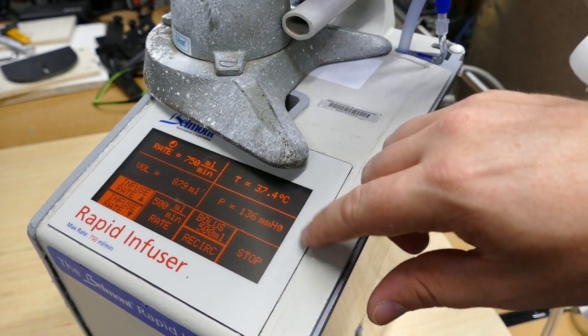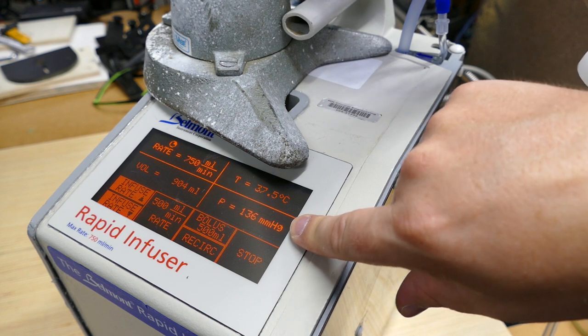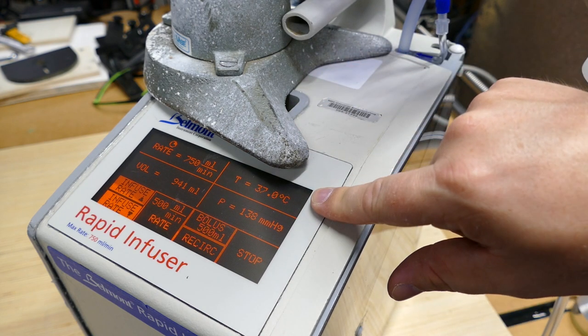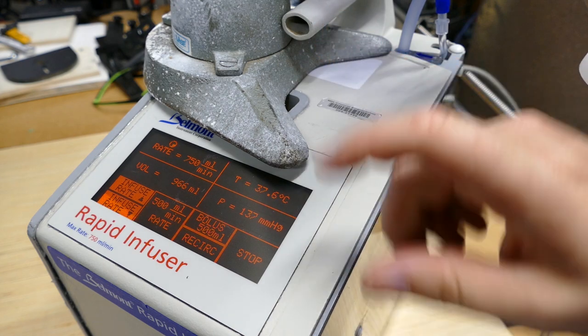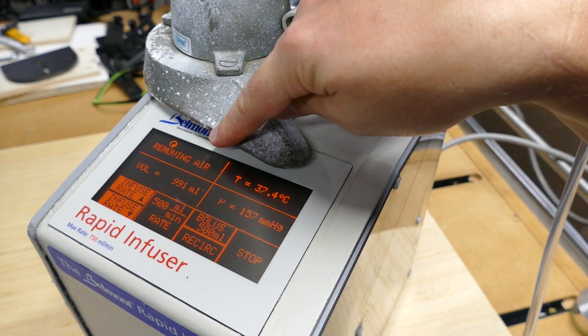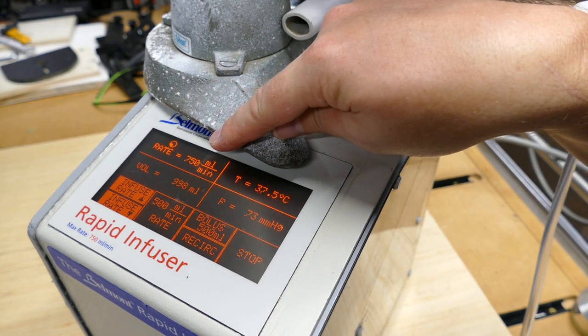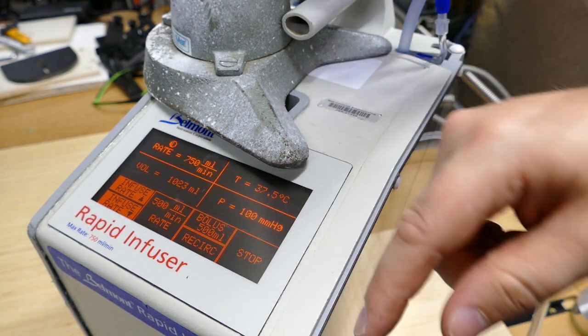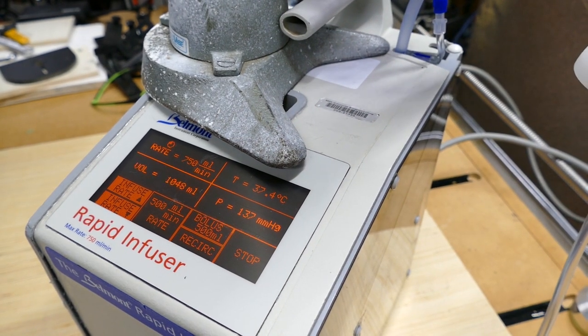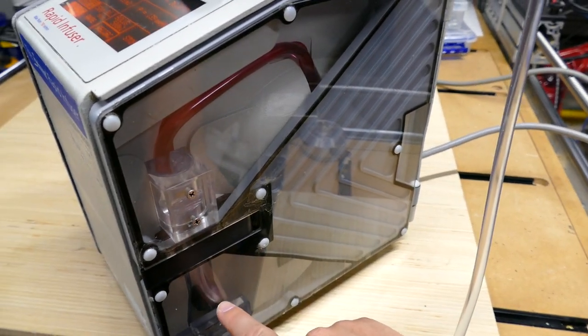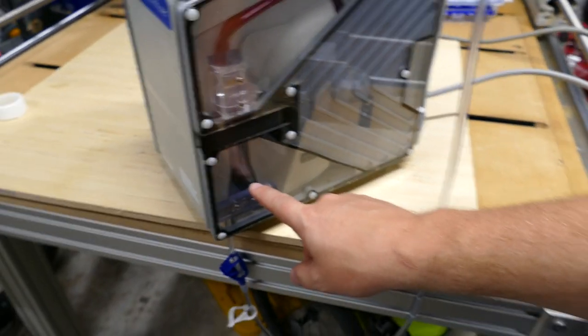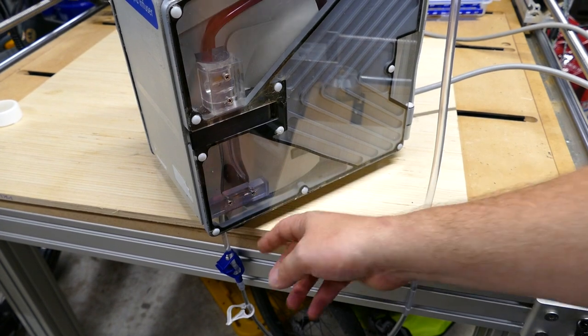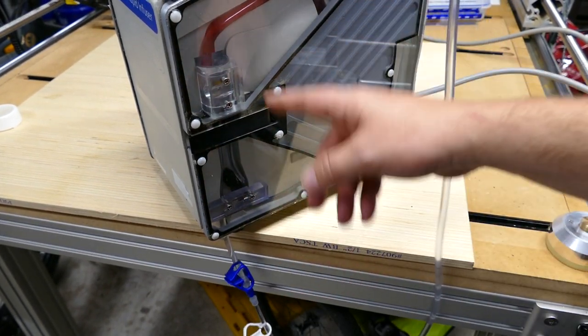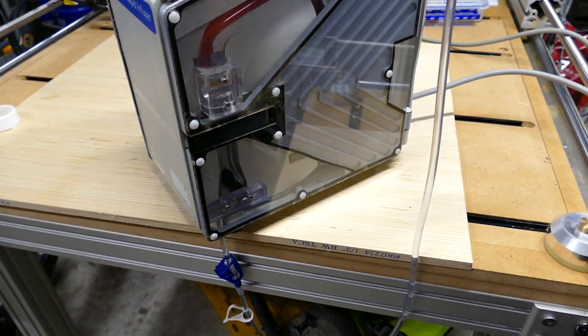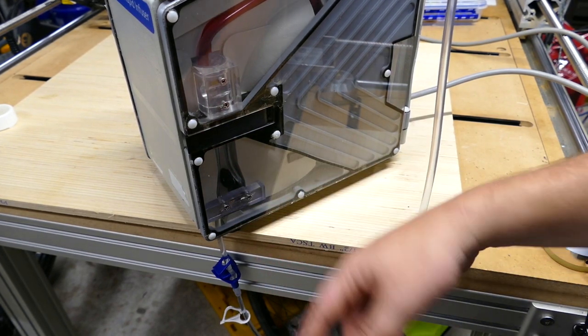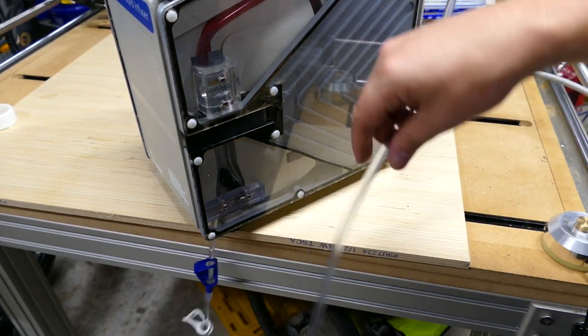You see here, at the higher flow rate, we have 135 millimeters of mercury. Our temperature is 37.6 degrees. Excellent. Flow rate 750 milliliters per minute. And you see what it's doing right there. Every once in a while, it kicks over the pinch line, which is right here. It happens once every couple minutes. The pinch will go over, it'll block off the patient side, it'll recirculate just to be sure that we get all the air out of the system, and then it goes right back automatically to recirculating to the patient.